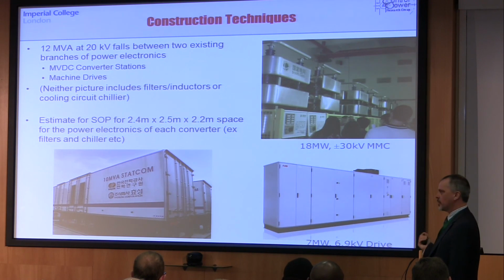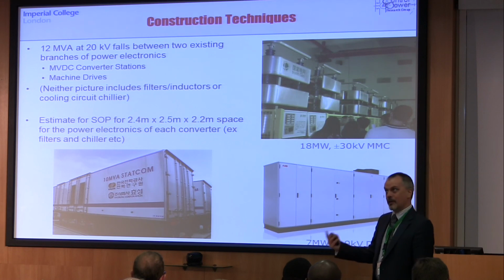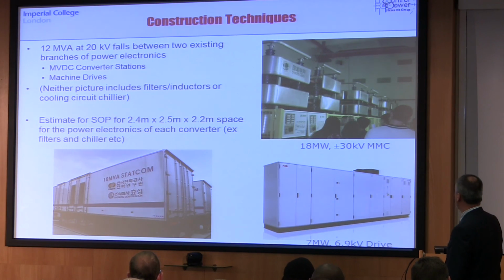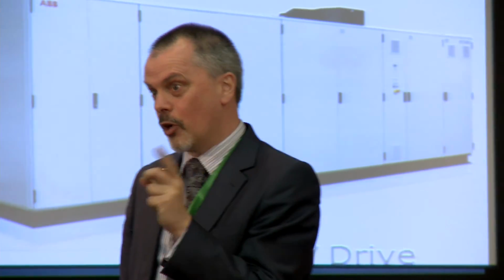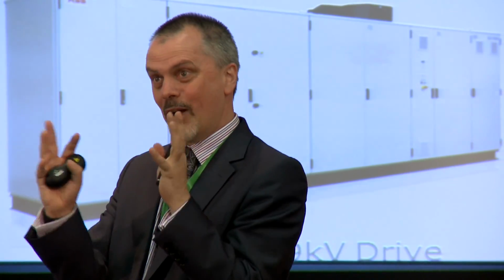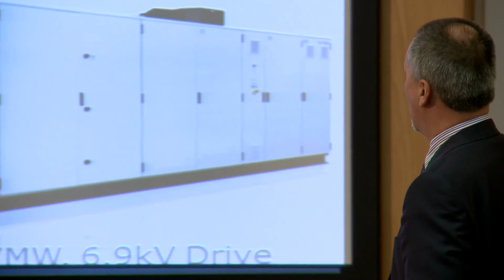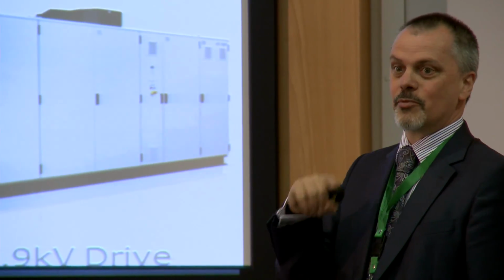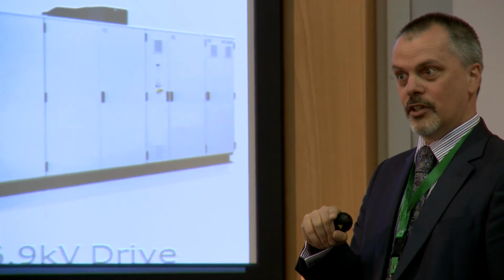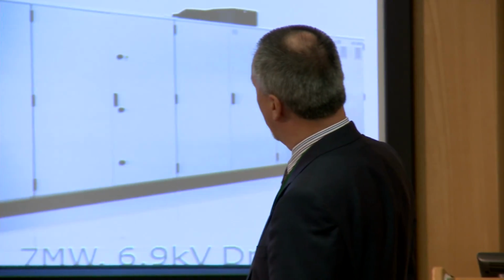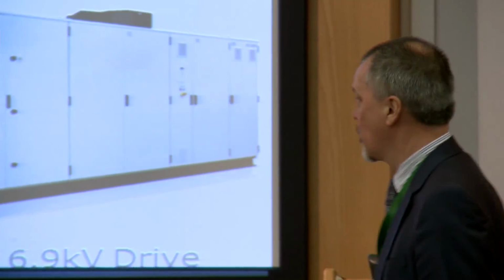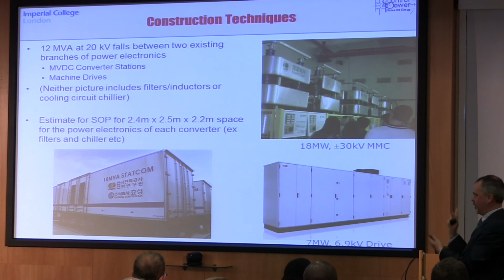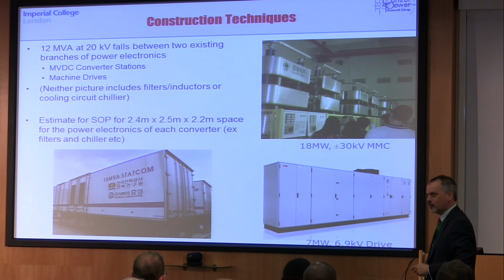It's, in fairness, probably a demonstration project rather than a product that is going to get rolled out. But you can see, even at 18 megawatt, this is a big valve hall. And actually, as Johan was saying this morning, you've got to watch how people are presenting power density. So this is the valve hall, this is the power electronics. There's another room the same size with the interface reactors in it, and there's another room somewhere else with the chillers for the water-cooled devices. So that's not the full view of the volume of this thing, and that's only 18 megawatt.